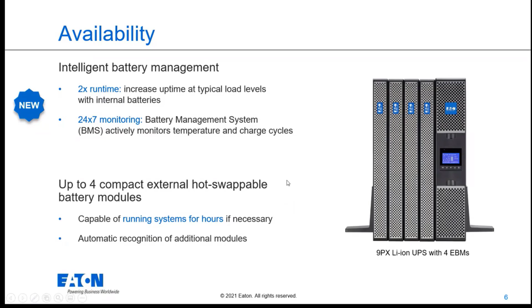Of course, we are still able to add external batteries, so EBMs. And you see on the right, this is a picture of a 9px lithium-ion with 4 EBMs. As with the normal 9px, you will be able to add up to 4 EBMs, and this will increase the runtime to multiple hours, depending on the load level. And there will be, as on the normal VRLA models, an automatic recognition of the battery module. So there is no need to set the number of EBMs through the LCD panel. This will be done automatically when plugging the EBM module into the UPS.